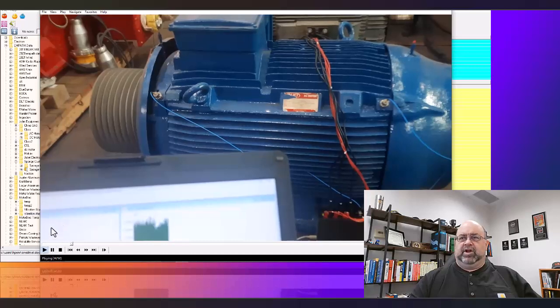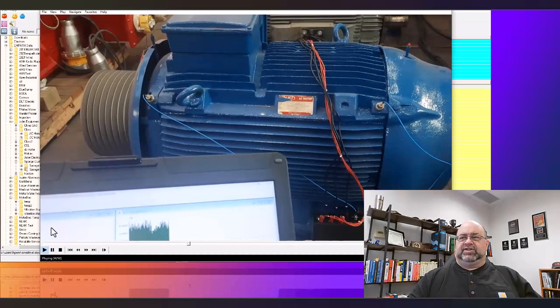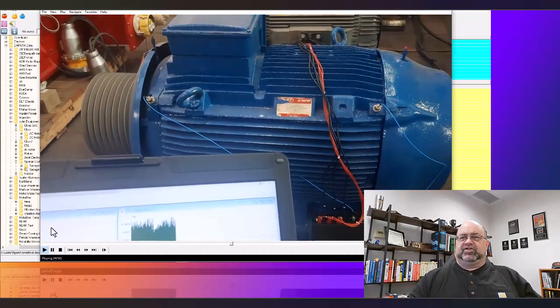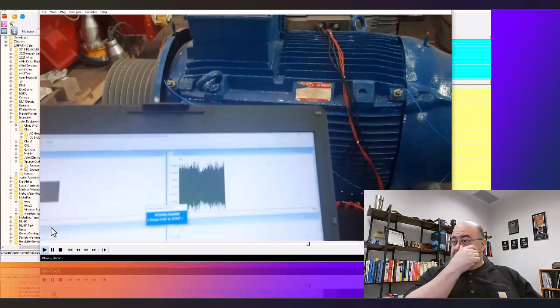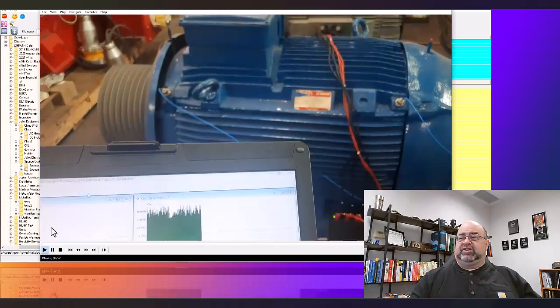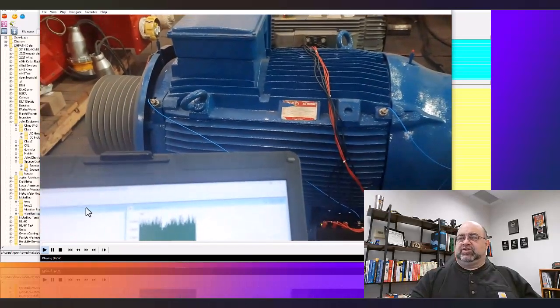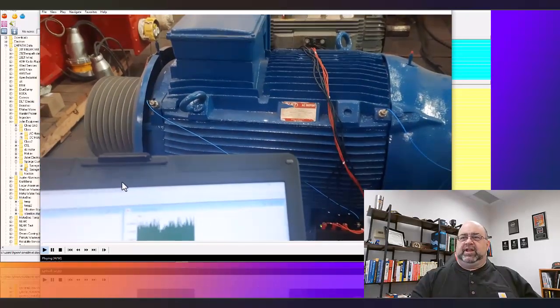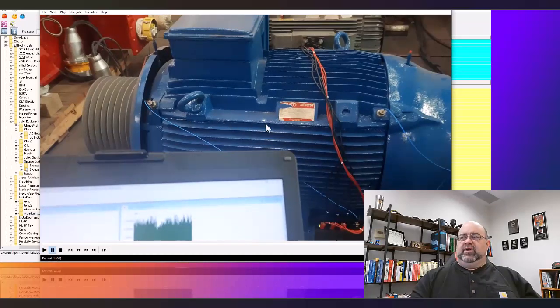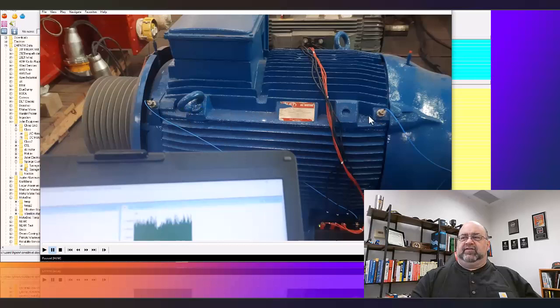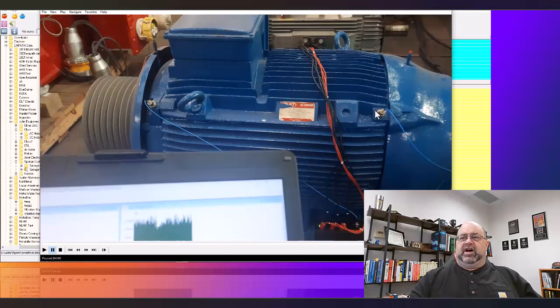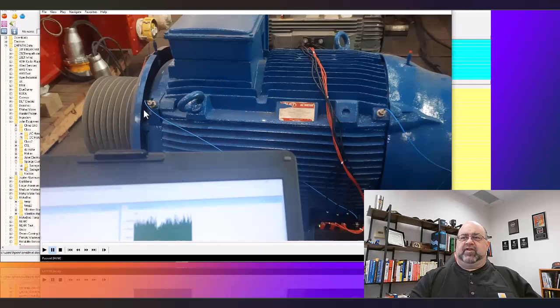Yeah it's running a little slow and a little jumpy but in any case we took this during the training class we did last week. And just to put it into perspective we took two 45 degree angle vibration data sets. I didn't do any more than that for this but we're going to use that to give us an idea. So we're going to take a back plane and a front plane, we have an obvious unbalance and we're going to go from there.